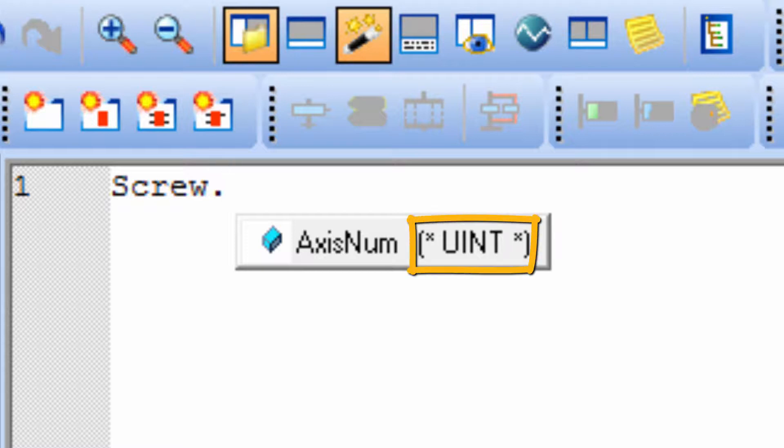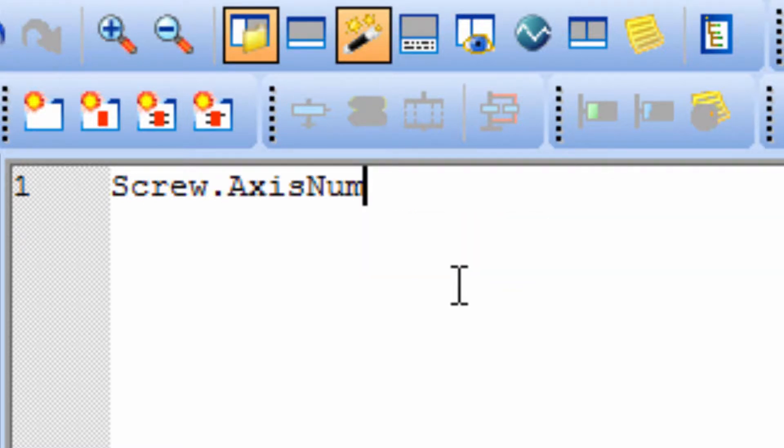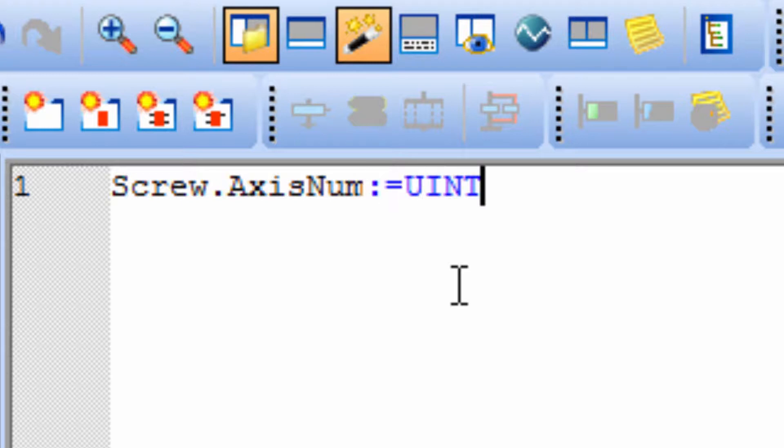Type dot and the Structure element appears. Notice the data type of the AxisNum element is uint, unsigned integer. Use the mouse or down arrow to select it and hit enter. To load an unsigned integer 1 for Axis 1 into the Structure element, use the syntax colon equals uint pound 1 for Logical Axis 1.